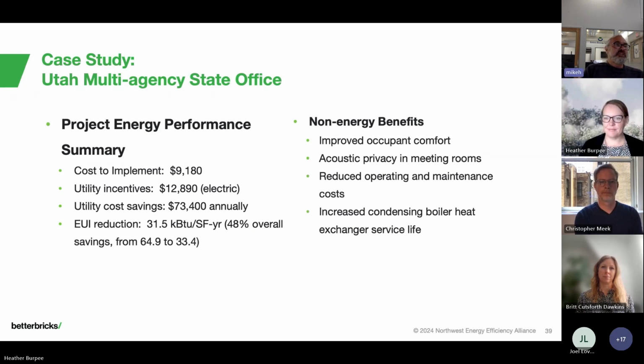On the non-energy benefit side, we saw significantly improved occupant comfort, particularly improved acoustical privacy in meeting rooms that underwent return air duct modifications, allowing doors to be closed during public meetings. We also saw significantly reduced operating and maintenance costs, particularly related to the ongoing failure of heat exchangers in the condensing boilers—they were losing a heat exchanger every 1 to 2 years due to deficiencies in the heating water system, at a cost of about $20,000 per heat exchanger. That is no longer happening.